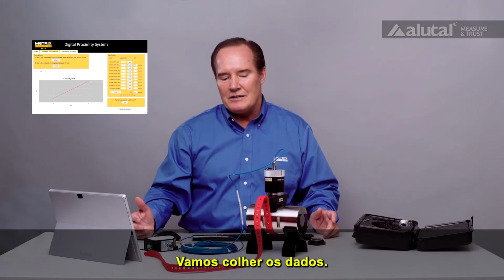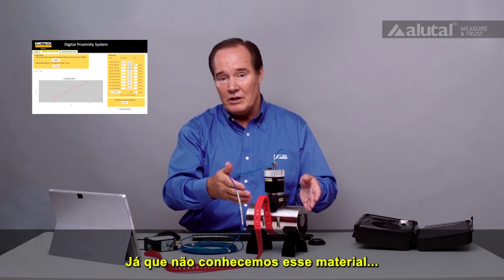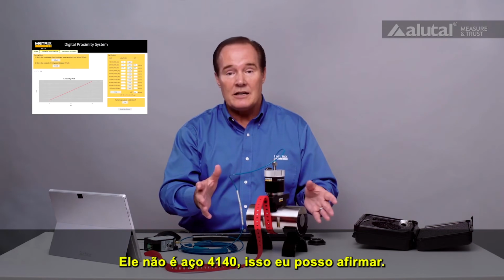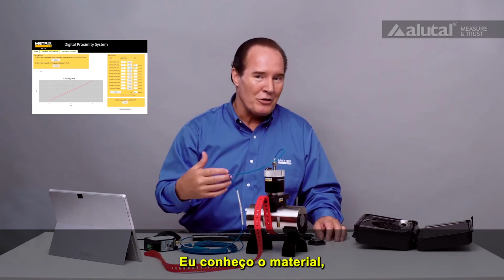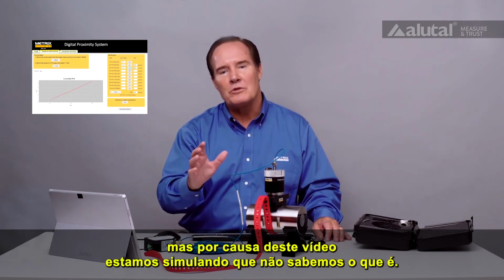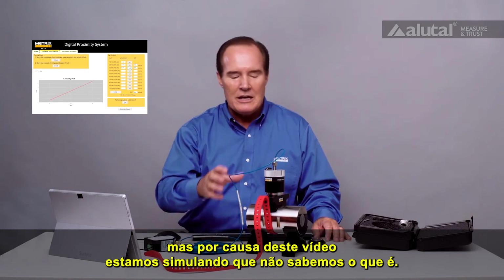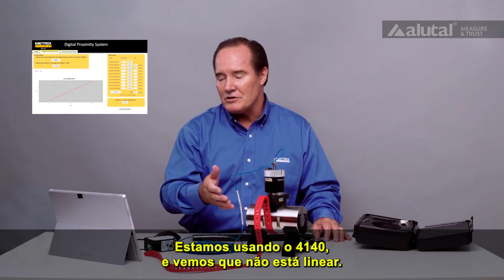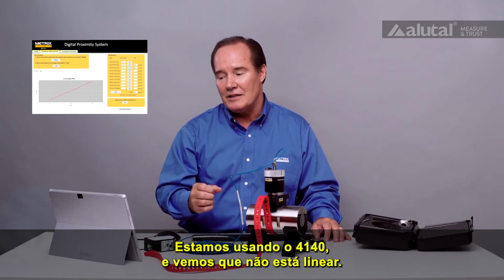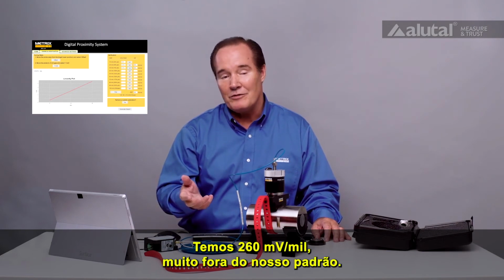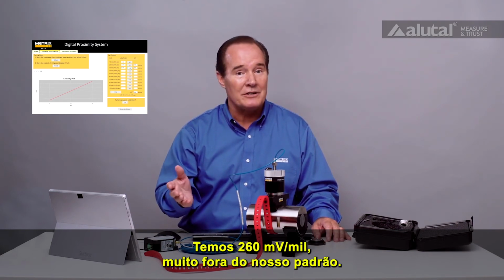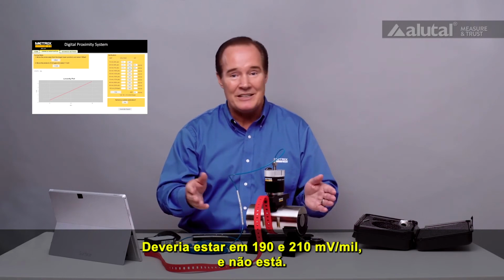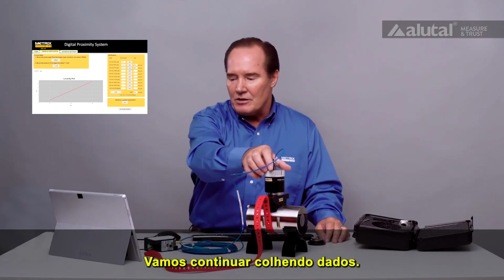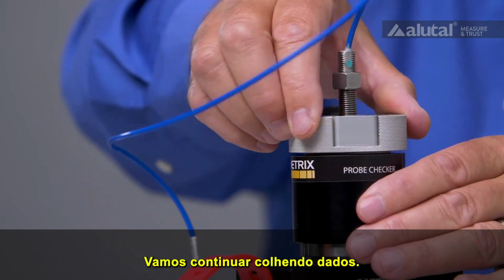And we'll take data, and since we don't know this material, it's not 4140 steel, I can tell you that right now. Really, I do know the material, but for the purposes of this video, we're simulating that we don't. All right. So we're using 4140, and you can see it's not linear. We have 260 millivolts per mil. That's way off from our standard. It's supposed to be between 190 and 210, and it's not. So we'll continue to take data.